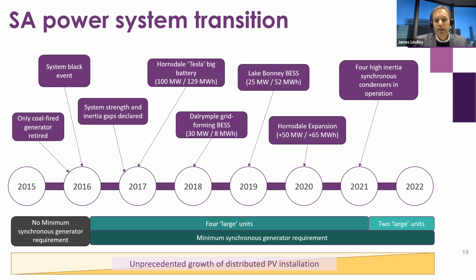While those synchronous condensers were being constructed, we had a requirement to maintain 4 large synchronous generating units online in South Australia. Since the commissioning of those units, we've reduced that requirement from 4 to 2. And so that's where we are now.